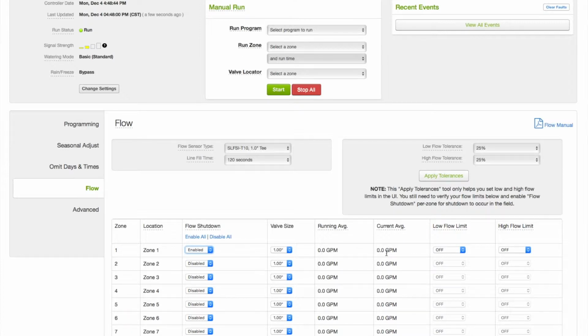If there are numbers populated in these columns, I can apply the tolerance. A 25% low tolerance or a 25% high tolerance. If I click on this and these numbers are populated, it will automatically set these values to this threshold of 25% low and 25% high. Keep in mind, if I set these tolerances but I leave this disabled, it turns the flow limits off. So if you set the limits or apply the tolerances and you leave this disabled, then this is going to come back returned as off on the next overnight update.